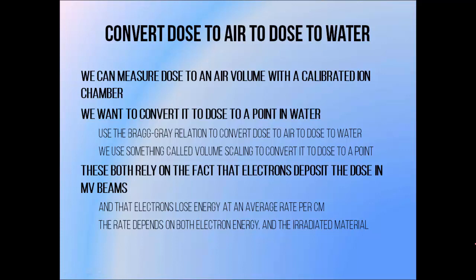In order to obtain a measurement of absolute dose with an ionisation chamber, we need to convert the measured dose to the air inside the chamber to dose to a point in water. We can obtain dose to air from measured ionisation chamber charge by multiplying the measured charge by the average energy required to produce that charge, and dividing it by the mass of air inside the chamber. The Bragg-Gray theory allows us to convert the measured dose to this air volume to dose to a volume of water instead, and we use something called volume scaling to convert dose to this volume to dose to a point.